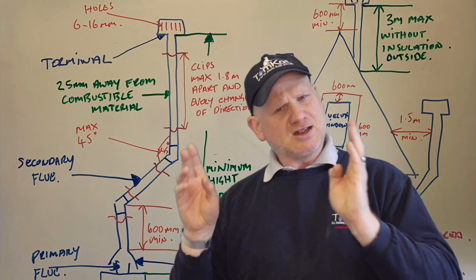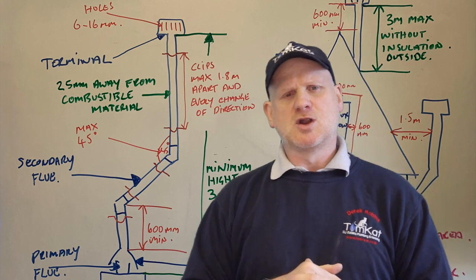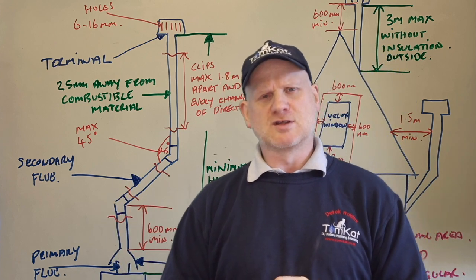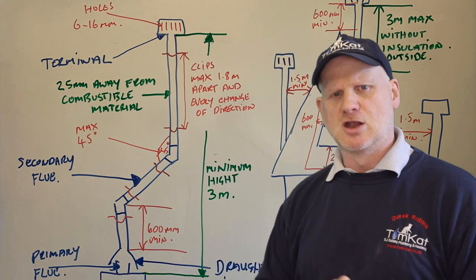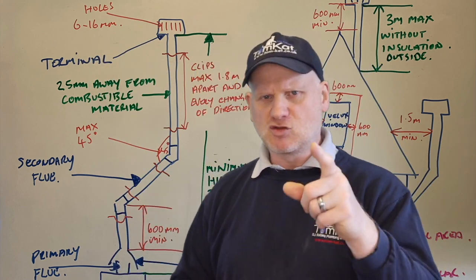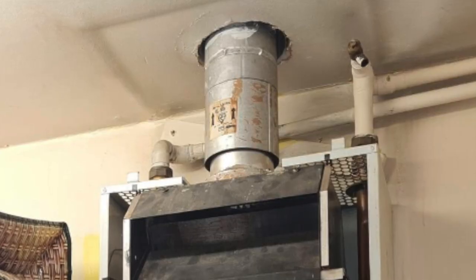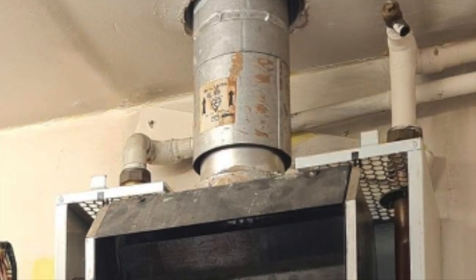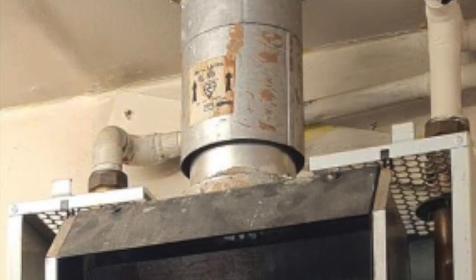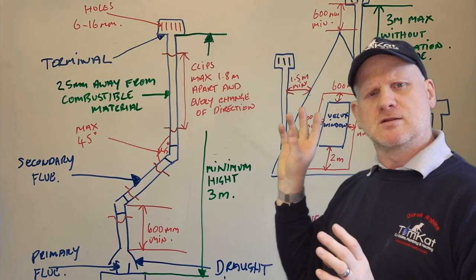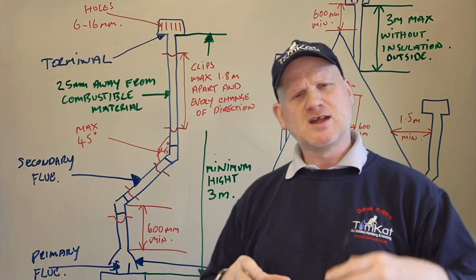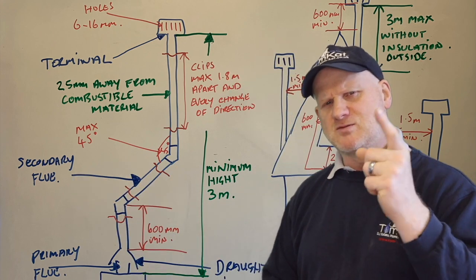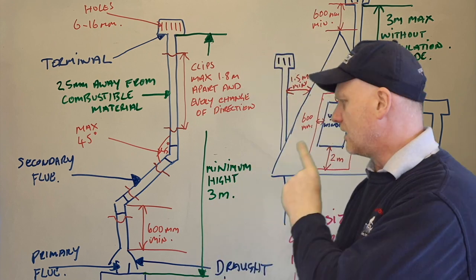The secondary flue must be twin wall. We can't have flue liner connecting to an open flued boiler unless it's a back boiler in a builder's opening. In the loft, it can't be flue liner — it has to be twin wall. We also can't use single wall flue systems in the loft. When connecting to the appliance, you must use an appliance adapter, sealing only the inner flue system to the appliance, not the outer. You must follow the arrows on the flue system. The maximum clipping distance is every change of direction and no more than 1.8 metres apart.